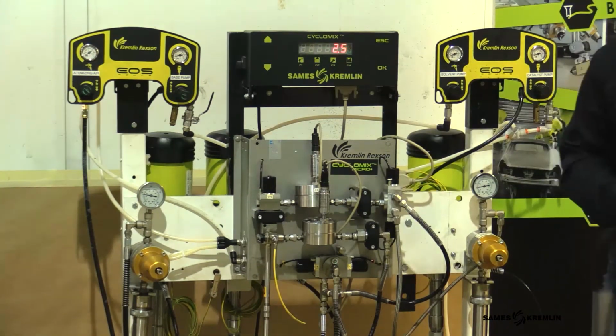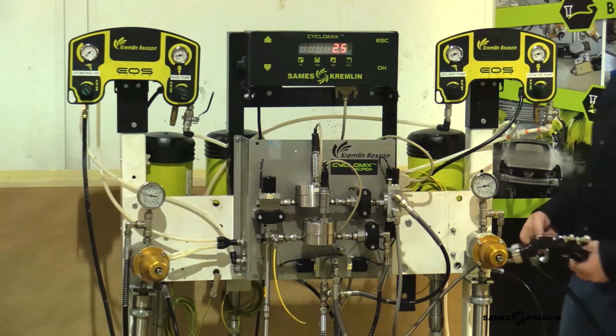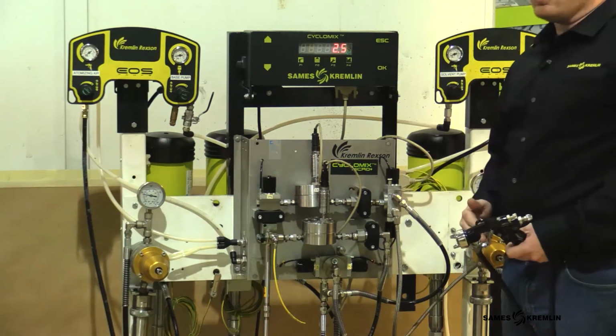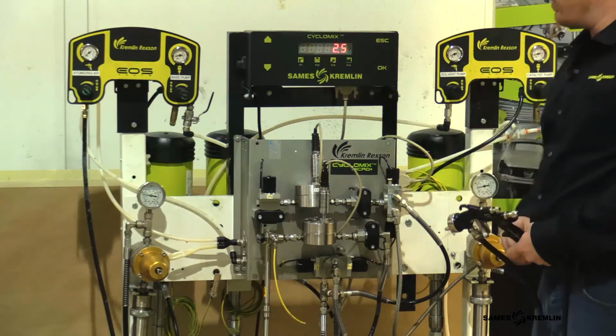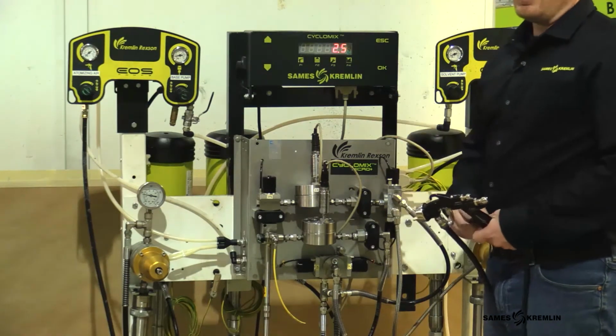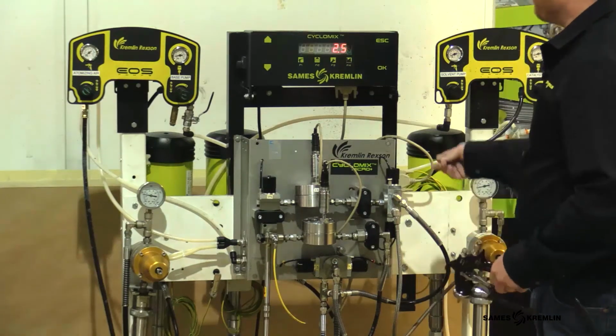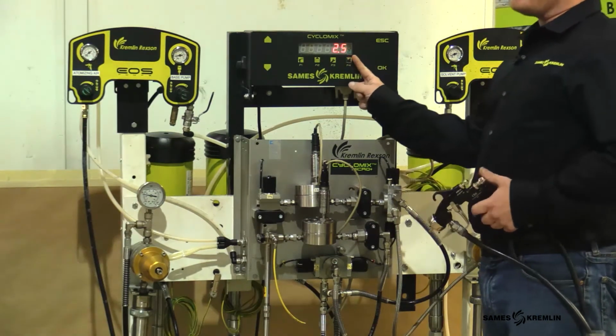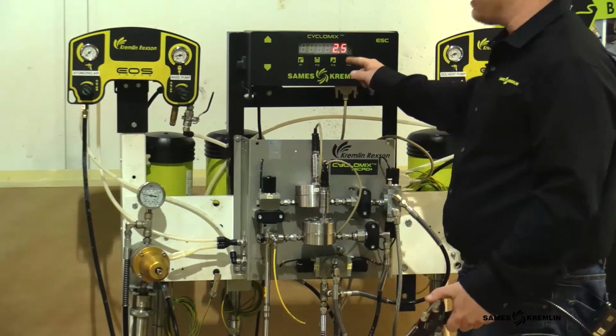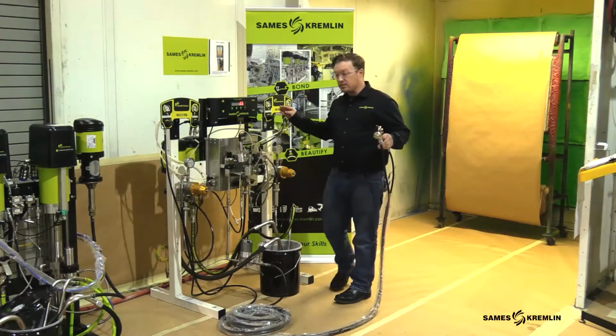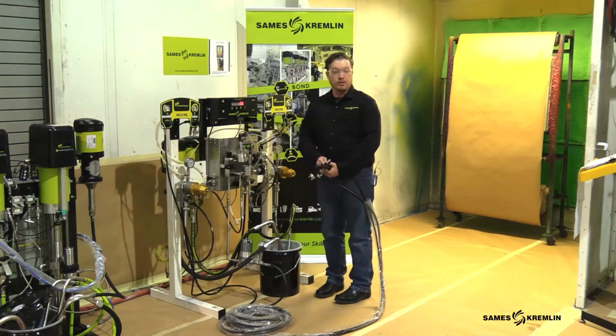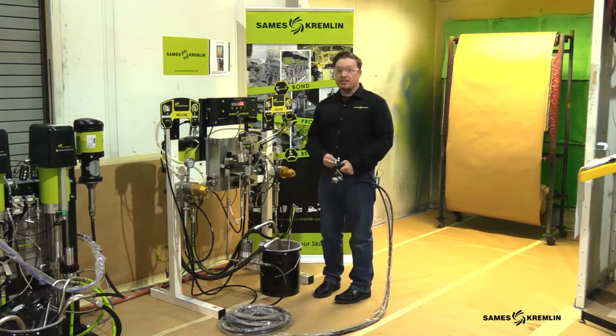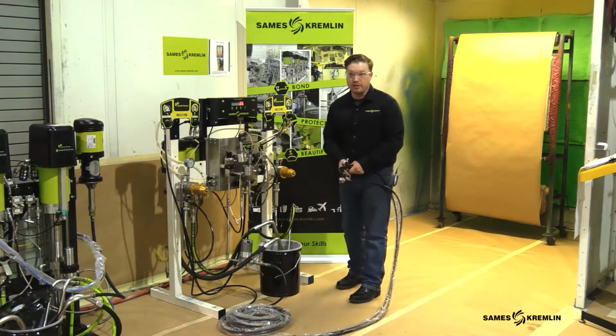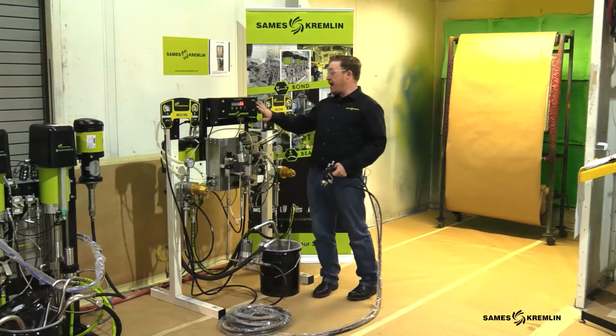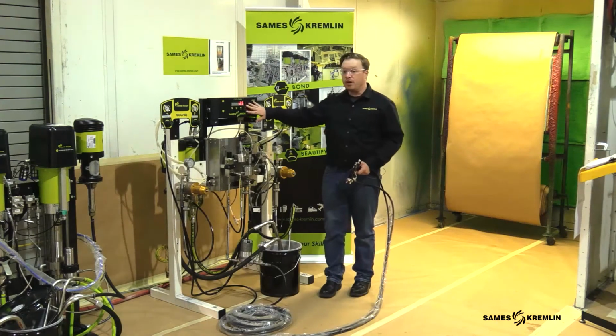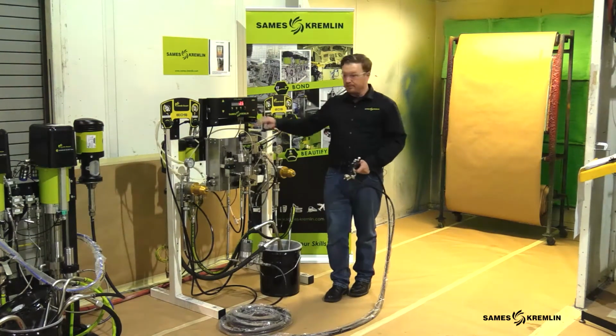P6 is going to be our tolerance. This is the mixing tolerance. We're allowed to go above and below our catalyst inject. So if we're at a 10% catalyst injection, our tolerance is 2.5% of that 10, not of 100. So it's a lot tighter than people would presume just by glancing over the documentation. There's a little bit more to it than that, and you need to be cognizant of the fact that this is a percentage of your ratio, not out of 100.